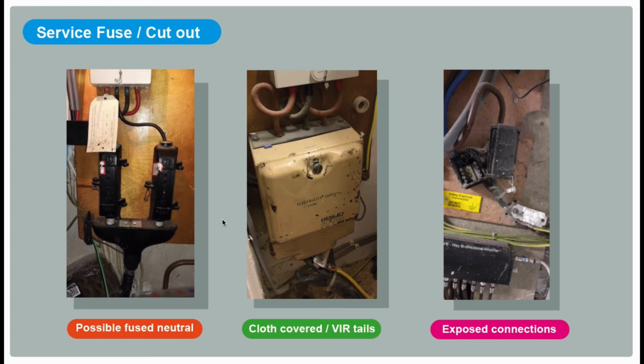Some other things to look out for when you're looking at the condition of the incoming services. Here we've got a possible fused neutral. This is where you've got a fuse in the incoming line, the live conductor, and in the neutral. This might have been swapped out years ago for a solid link, but there's a possibility there could be a fuse in there. You need to investigate that with the DNO because a fused neutral is potentially dangerous.